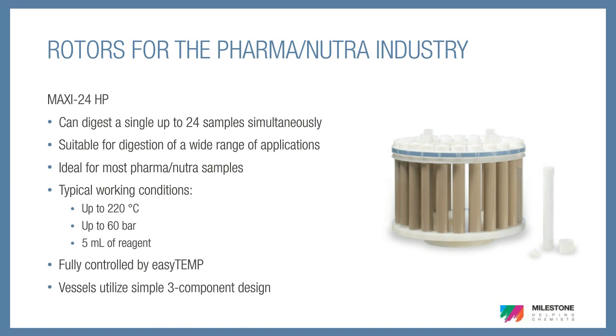This rotor can process a single up to 24 samples at once. Its higher temperature and pressure capability of 220°C and 60 bar makes it ideal for handling most pharma and nutra samples. This rotor uses easyTEMP technology to control the temperature. With easyTEMP, the temperature of every vessel is monitored and controlled off of the hottest. This is not only for safety reasons, but also to ensure our vessels do not vent excessively, which is important since many of you will be analyzing for mercury. The vessels utilize a simple three-component design, only requiring simple hand-tightening to assemble and close. This makes it ideal for busy lab environments where ease of use is critical.